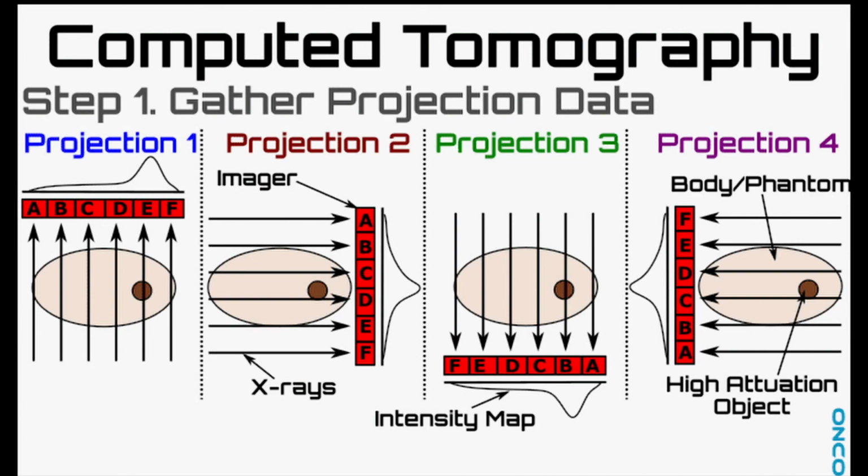Okay, so at this point we have just an expanded explanation of the previous slide. We have an X-ray tube down here. All the X-ray beams are going through here, and here's the patient with something that they're trying to observe. These are the detectors, and you will see that the plots of the output from the detectors reflects the amount of attenuation of the X-ray beam.